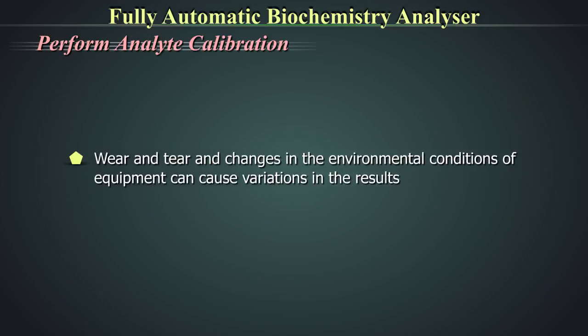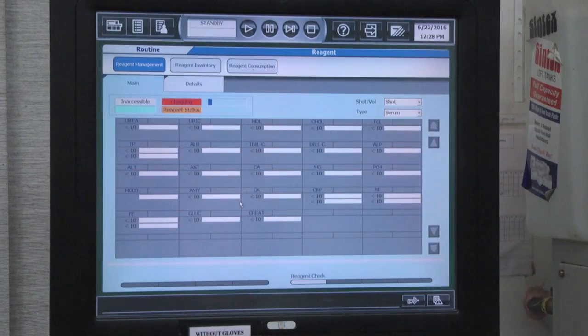Equipment wear and tear and changes in environmental conditions can also cause variation in results. For more details, refer to the training module on equipment management. Monitoring of calibration is important. The reagent blank will tell how the reagent is preserved, and reagent calibration history will tell how much readjustment the reagent needed while in use. It is important to monitor the performance of each lot of reagent; calibration is required when a new lot of reagent is put into use. The calibrator must be stored as per manufacturer's instructions, with multiple pictograms on the vial indicating storage and handling conditions.